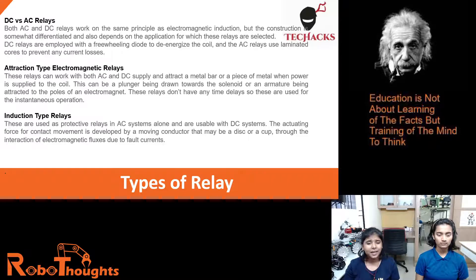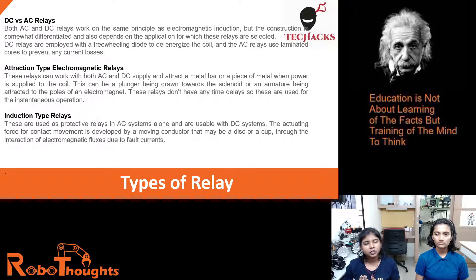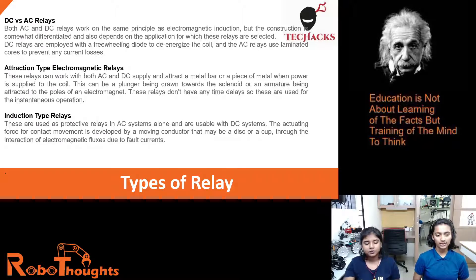Attraction type electromagnetic relays can work with both AC and DC supply and attract a metal bar or a piece of metal when power is supplied to the coil. This can be a plunger being drawn towards the solenoid or an armature being attracted towards the poles of an electromagnet. These relays don't have any time delays, so they are used for instantaneous operations.